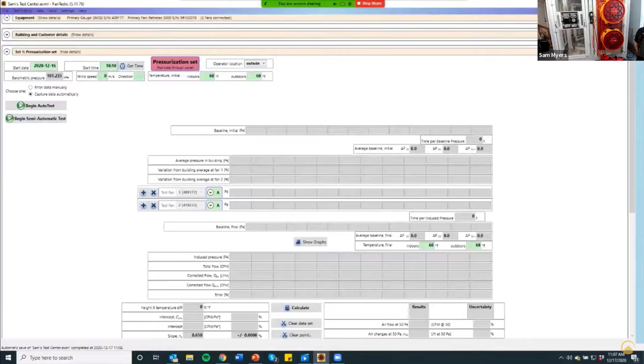I want to go ahead and tell you guys about this now, because when I get these fans ramped up, it might get a little loud and might be hard to hear me. So one thing I want you to pay attention to is the fan speed, and notice the different colors. Obviously red, it's not running. Yellow, it's not going to pull great data. It's not going to have enough fan pressure inside the fan shell to generate a good, accurate flow calculation. But if it's in this green, it's going to be okay. And so that way, if I'm running a multi-point test and I'm staying in the green from 60 and then drop it down to 50, the speed's going to drop as I drop pressure. But then say if I get down to like 20 pascals and it's here, I'm going to want to go ahead and stop that test, change the range, which I can just do here in the software, mimic it on the fans themselves, and then resume, and then that fan speed will ramp back up.